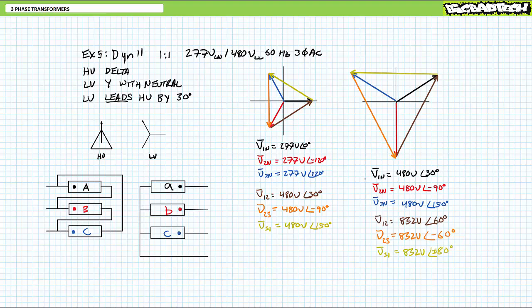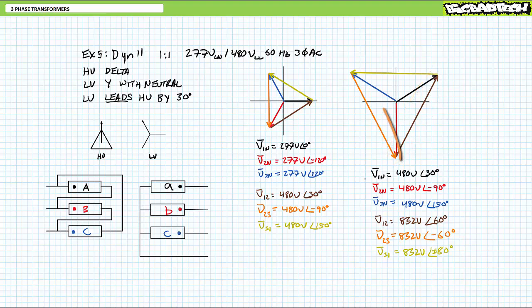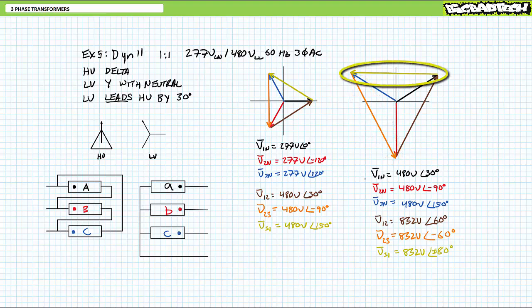While it's not necessary, while this example is still in front of us, we could calculate the resultant line-to-line voltages at the secondary — understanding they will be roughly 1.73 times the line-to-neutral voltages and lead them by 30 degrees. Line one with reference to two at the low voltage secondary will have a value of roughly 832 volts at an angle of 60 degrees. Line two with reference to line three will have a value of roughly 832 volts at an angle of negative 60 degrees. Line three with reference to line one will have a value of roughly 832 volts at an angle of positive or negative 180 degrees. This goes to show that even though you're using a one-to-one transformer, and even though this is called the low voltage side, the connection configuration can influence phase shifts such that resultant voltages are substantially amplified.